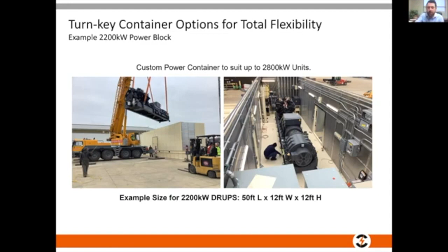This is a 2.2 meg unit, but this could be medium voltage, could be 2.9 meg. As I mentioned earlier, it's standard air in, air out - if you saw this, you wouldn't know it was a Drups versus a generator. I think it's a roof-mounted radiator. We provide the small power, the lighting, and we've done the fuel system. That was custom turnkey by HiTec. So from your perspective, it's very much a single partner - we have all our suppliers.